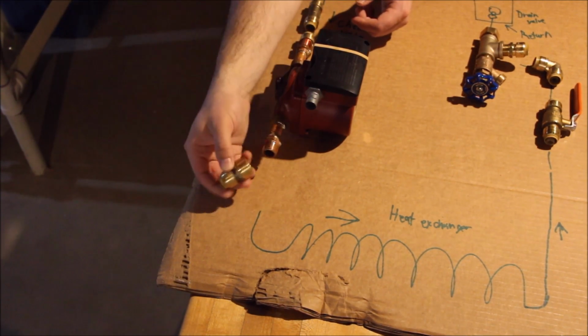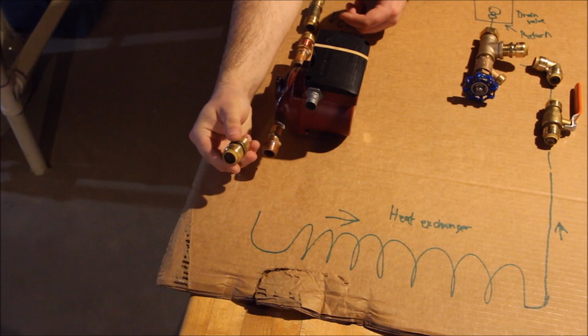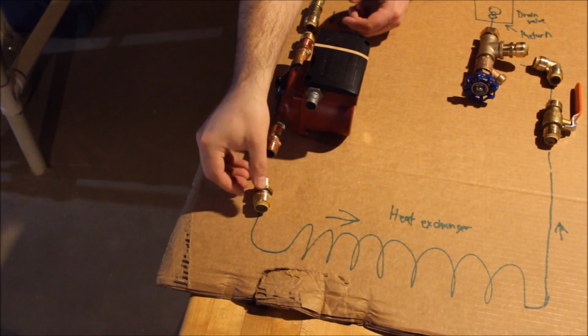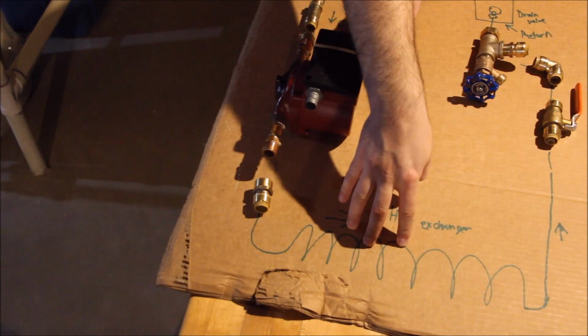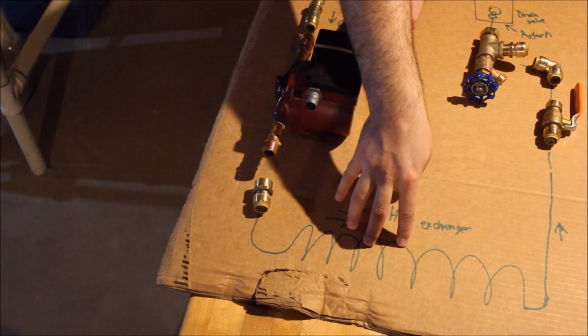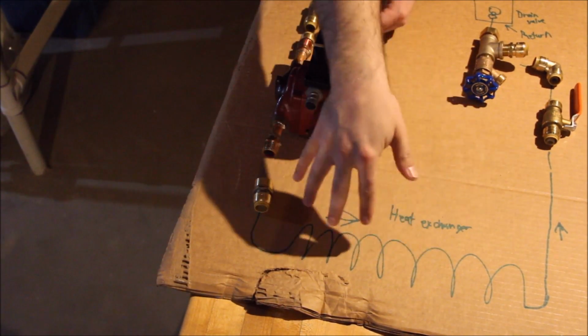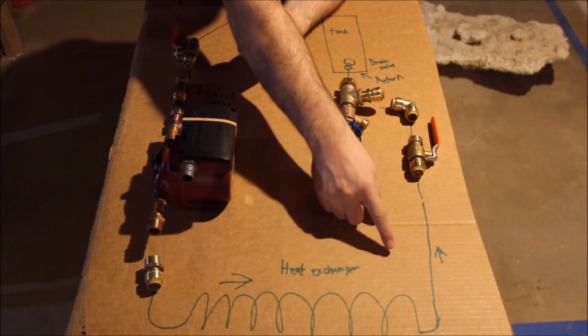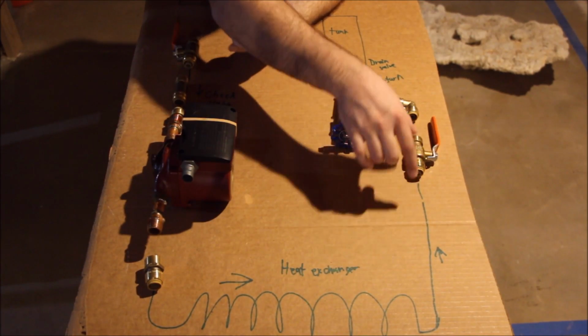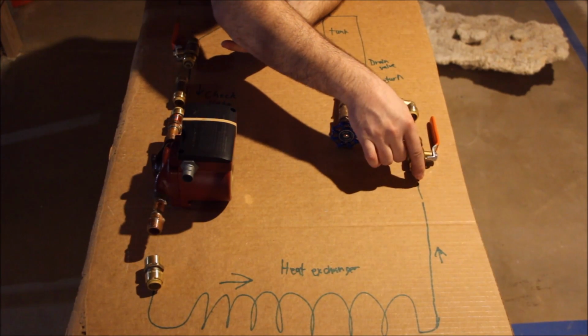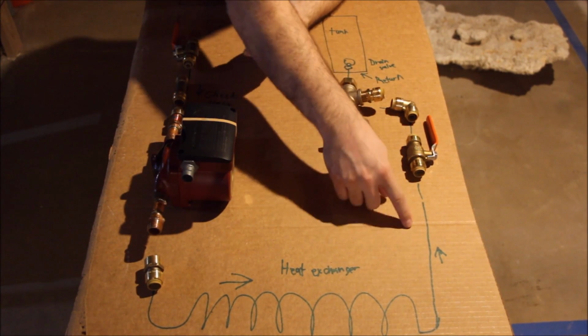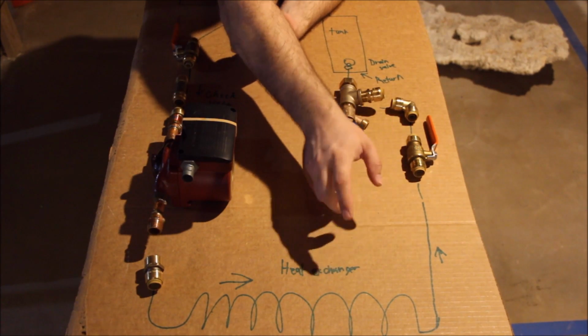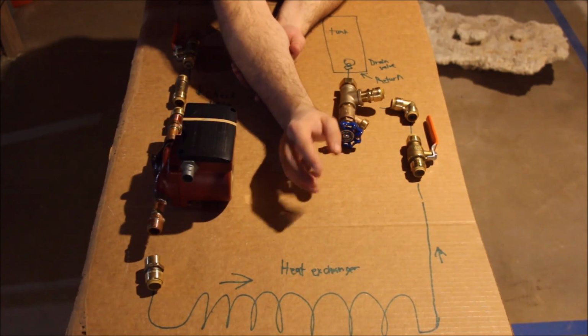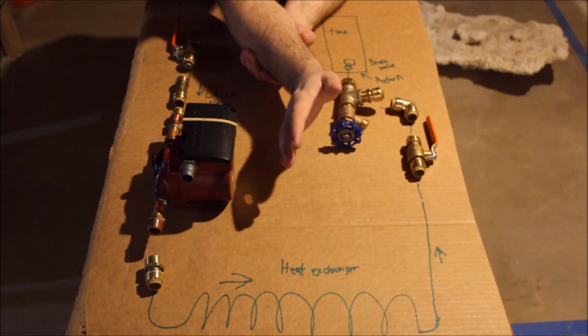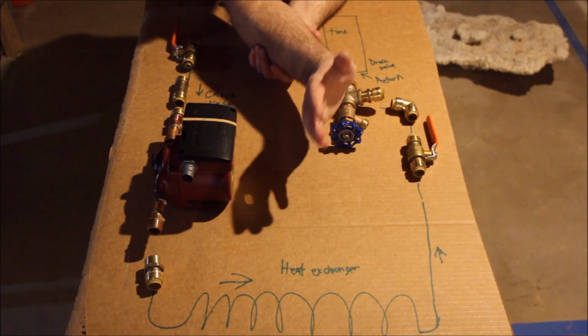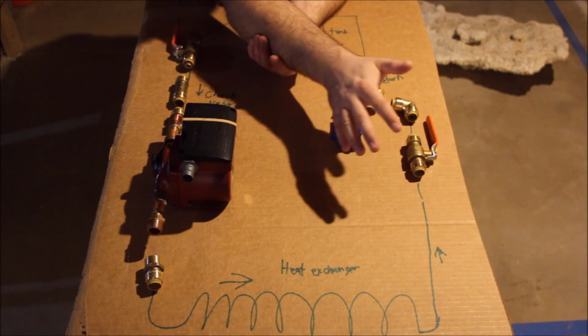From the pump, it's again going to go into another female threaded into a compression fitting, and then into the heat exchanger, which sits in the 120 gallon sump. This heat exchanger is what's going to be heating the tanks for me. After we exit the tanks off the heat exchanger, I'm going to go back to the hot water tank. This line that comes out of the sump and back, and even the supply line potentially, I'm going to insulate so I don't get heat loss into my basement, making me more efficient about using the hot water.